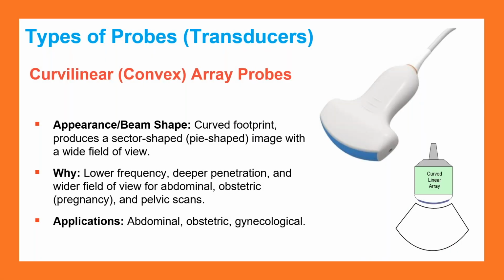Curvilinear or curved probes, abdominal OB/GYN probes primarily. Abdominal is a general description. They are normally lower frequency because they require a lot of penetration. Okay, the curve is a wide angle, so you have a wide angle of view when you're looking at it. And again, we use it a lot for OB/GYN, babies. So we need a wider angle of view.